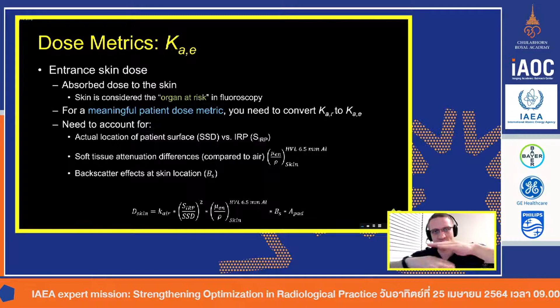And then, of course, there's a bunch of things in the path. If the patient is laying on a table, they're probably laying on some kind of cushion or pad, and that table and that pad are going to attenuate the radiation beam. So we need to take into account all of the objects between the X-ray source and the patient.